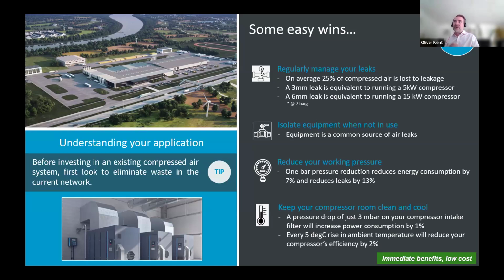Isolate that production equipment from our compressed air net. Then we could do an audit on the working pressure of our compressed air system. Do we need to be running our compressed air system as high as we actually run it? Could we reduce our compressed air system average pressure by half a bar? Could we even reduce it by 1 bar? And for every bar pressure reduction, you will reduce the direct energy consumption of your compressed air system by 7%. So not an inconsiderable amount.